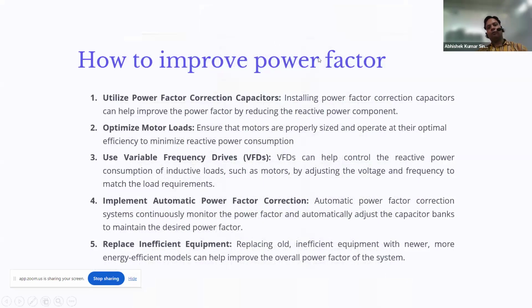Now, how to improve the power factor? It can be improved by placing capacitors and by having an optimized motor load. Optimized motor load means that if the requirement is 50 kilowatt, then you need not have an 80 kilowatt or 100 kilowatt motor; buy a 50 kilowatt motor only. Otherwise, if you buy a big motor, it will take extra magnetizing current, which requires extra kVAr, and we have to generate that from our end, which is definitely a cost. Then there is the use of VFDs. As we know, a VFD controls the power factor, but it also produces harmonics.